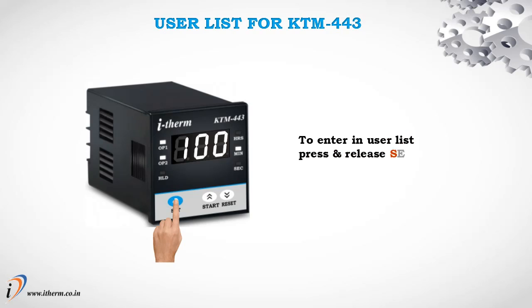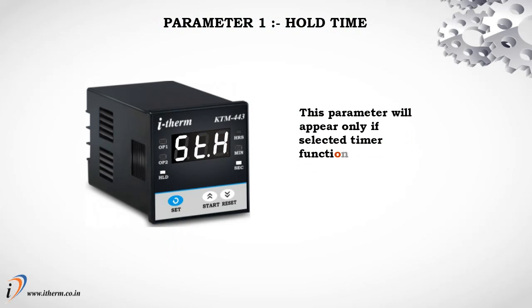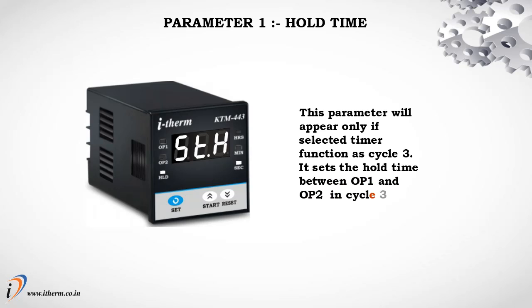User list for KTM 443. To enter the user list, press and release the set key once. Parameter 1: hold time. This parameter will appear only if the selected timer function is cycle 3. It sets the hold time between output 1 and output 2 in cycle 3.